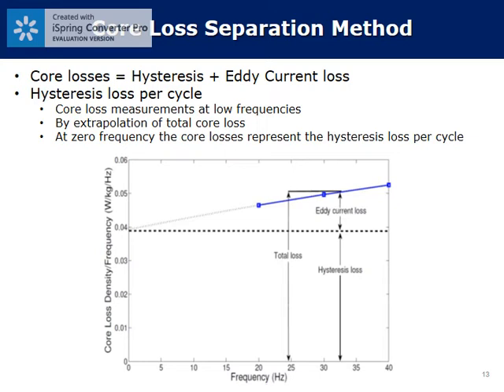As we know, core losses have both hysteresis and eddy currents, which form the total core losses of your machine. We wanted to separate these two. What you normally do is measure your total core losses by frequency. For example, we measured at around 20 hertz, 30 and 40. Usually, this measurement should be at low frequencies. Then you extrapolate to the y-axis. Where you cut the y-axis is where you get your hysteresis losses. And from there, those are the eddy currents.